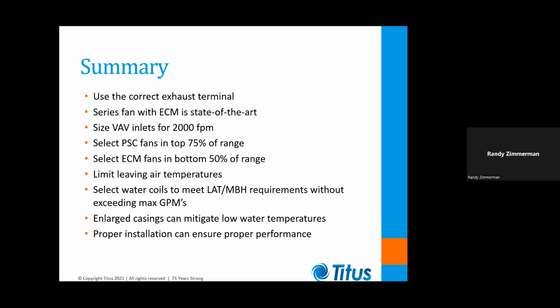You want to use the correct terminals for exhaust. You want to use series fan powered with ECM because that's really the state-of-the-art fan-powered terminal unit. You want to size VAV inlets for no more than 2,000 feet per minute. You want to select PSC fans in the top 75% of their operating range. Should say 25%, excuse me. And we want to select our ECM fans in the bottom 50% of the range.